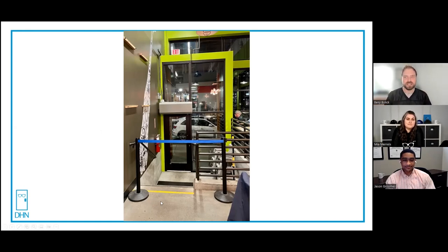Right? It's definitely not ADA compliant either, though I'm guessing the other people could go out other doors. But in the case of an emergency, if someone walked through the front door with a gun, this is your side exit. I know there's a back exit as well, but if anyone's sitting at this cafe, this is going to be their running point to escape. You can't see it in the photo, but I went around to the outside and double checked it, and it is deadbolt thrown, locked. So it's not even free egress if you can get past the blue tape.